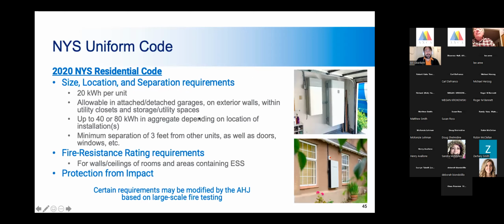Before going into the fire code, let's go to the residential code. The residential code has a very small purview as it relates to energy storage systems. We've got size, location, and separation requirements. So we're maxed out at 20 kilowatt hours per unit. To put that in context, if folks have seen a Tesla Powerwall, which is this on the bottom, that's 13.7 kilowatt hours. So well below the threshold, and that is one unit. So we've got a 20 kilowatt hour unit max. We're only going to allow residential installations on attached or detached garages, exterior walls, and within utility closets and storage and utility spaces. By code, those are the only places in a home that energy storage systems are allowed to go. Although utility closets and storage and utility spaces are ill-defined, and they can really be a broad swath of places, but those are really the places that we are allowed to have energy storage.